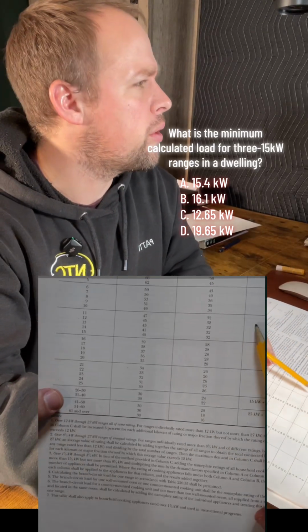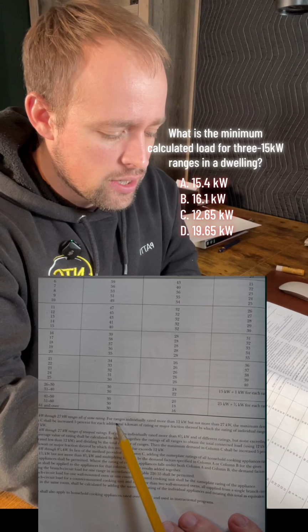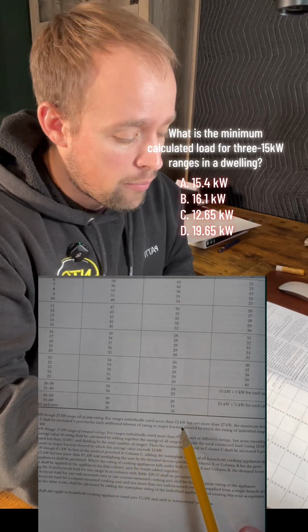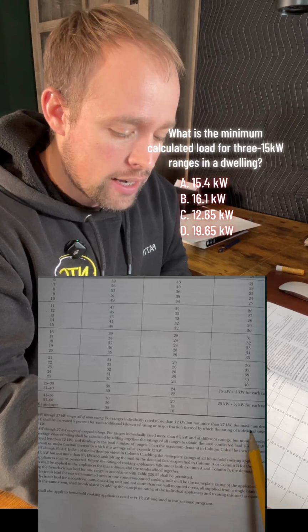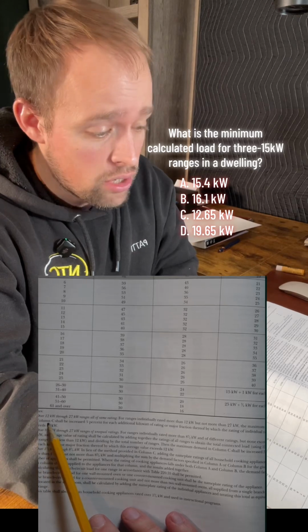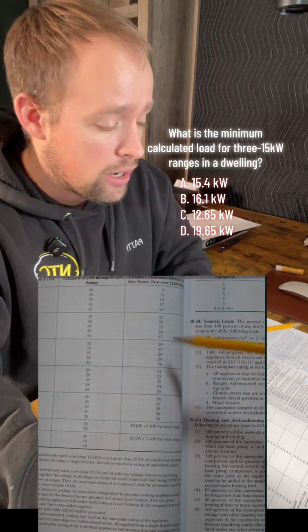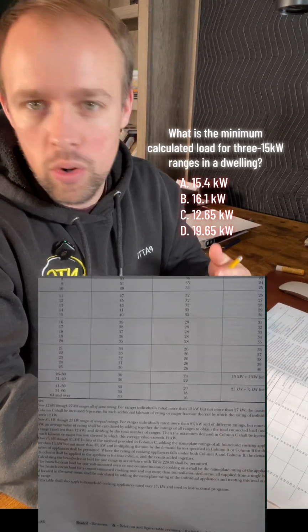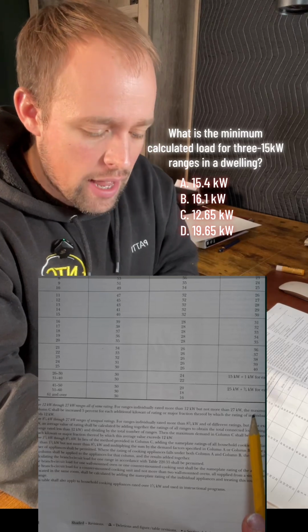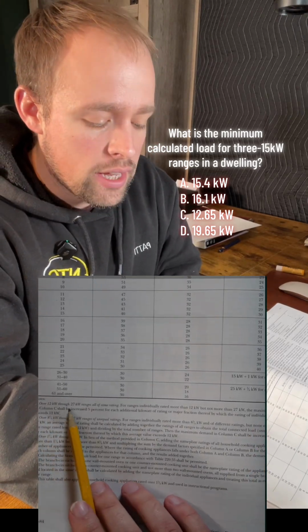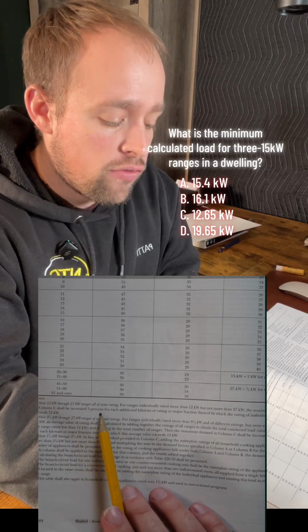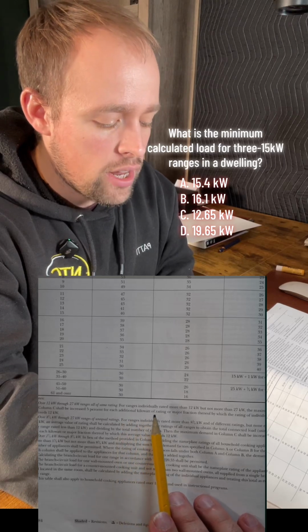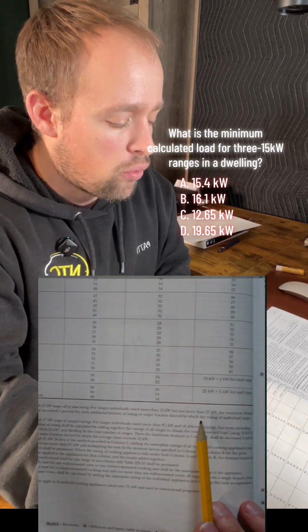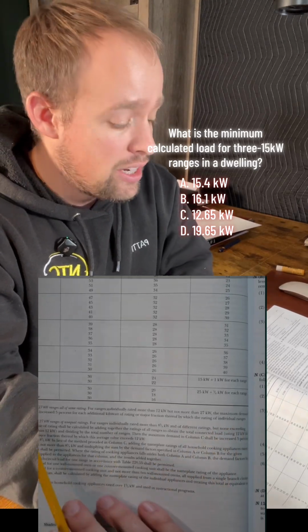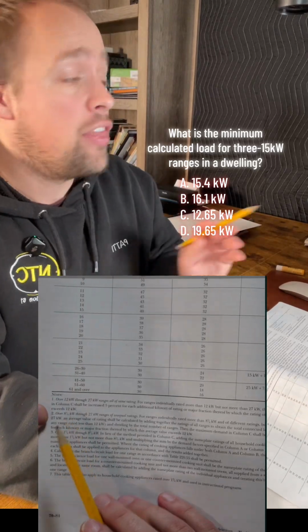So let's read note 1, okay? It says, for ranges individually rated more than 12, but not more than 27, the maximum demand in column C, okay, so we're still using a value that's in this column C here, but let's continue reading to figure out what we do with that number. So again, the maximum demand in column C shall be increased 5% for each additional kilowatt of rating or major fraction thereof, by which the rating of the individual ranges exceeds 12 kW. That is a mouthful, isn't it? You're probably thinking, what the heck does that mean?